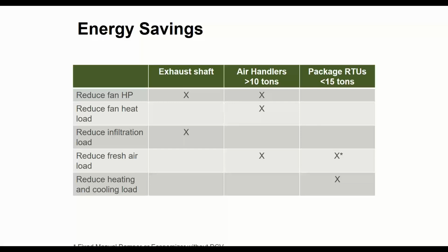And then on air handlers and package units, we're showing those separate. I mean, they really are kind of the same thing. It's just that the benefits are different based on where things are located sometimes. But for either one of these, you will be able to reduce your fan-related heating load. You'll be able to reduce the fresh air load, and you'll obviously reduce heating and cooling loads.